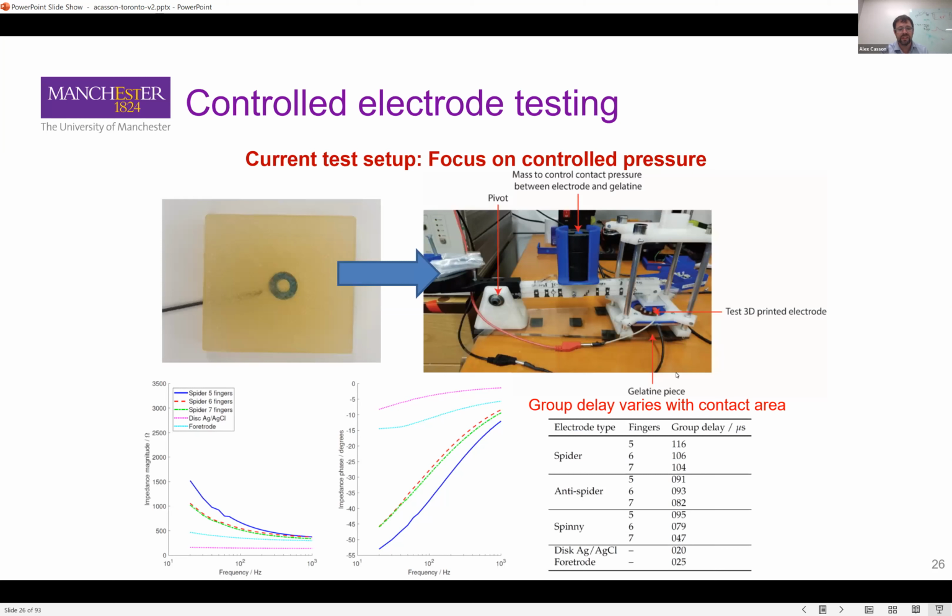We know what the comfortable pressure range is for putting an electrode against the head, and so we can look at how the noise scales with contact force and things like that. Something we found, which we weren't quite expecting, was that we know the contact impedance changes as you put electrodes against the head more. Essentially, if you're willing to push something in till it hurts, you get a better contact.